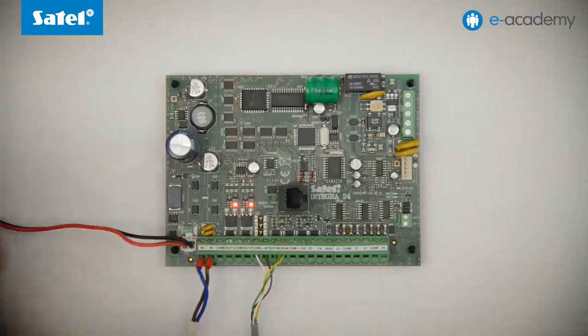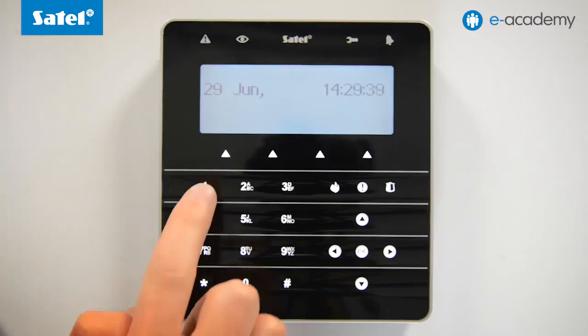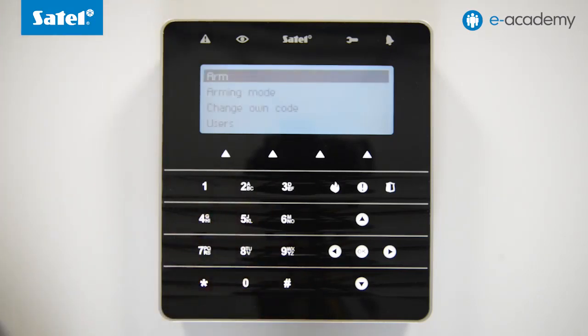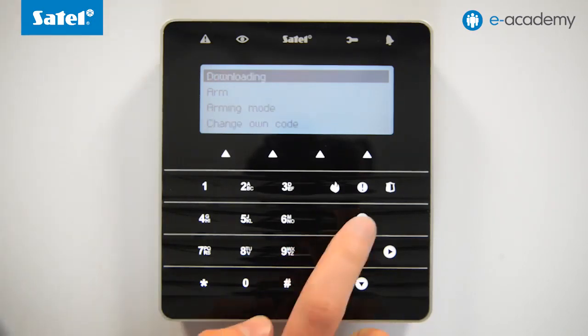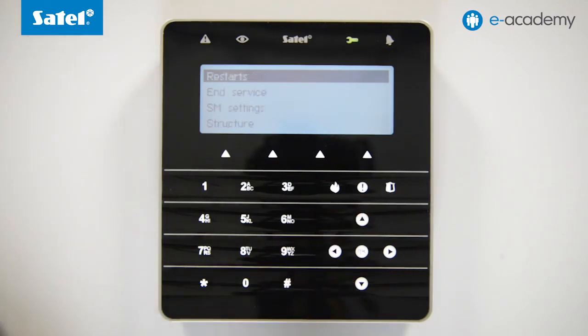Now we will show you how to download such a file into the control panel. We start by connecting the control panel to the computer by means of the USB RS converter. The next step will be to enter the service code on the keypad and confirm it using the asterisk button. Select Service Mode and the Restarts tab in it, then select Restart All.